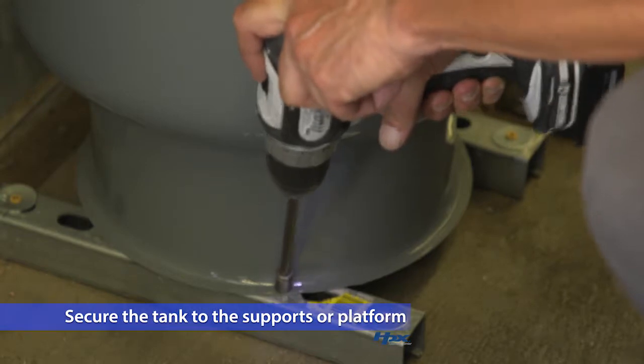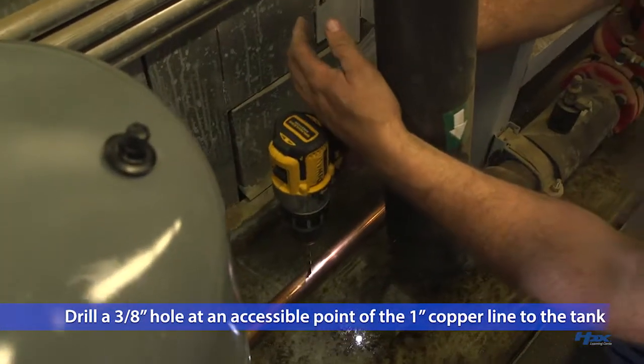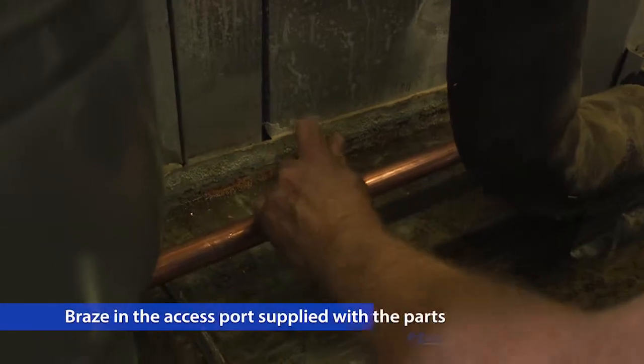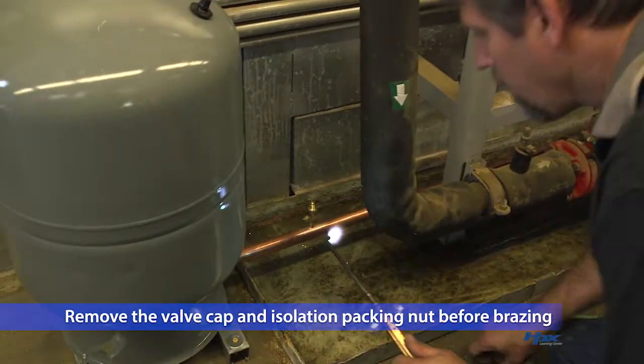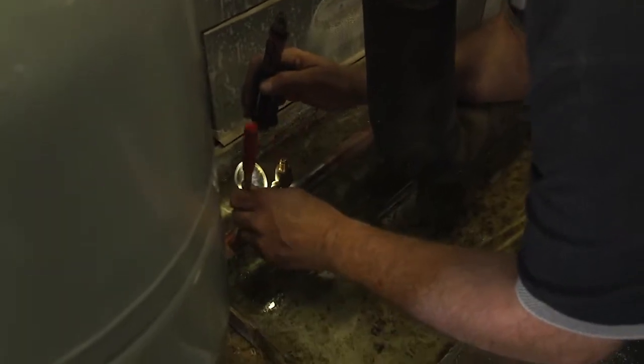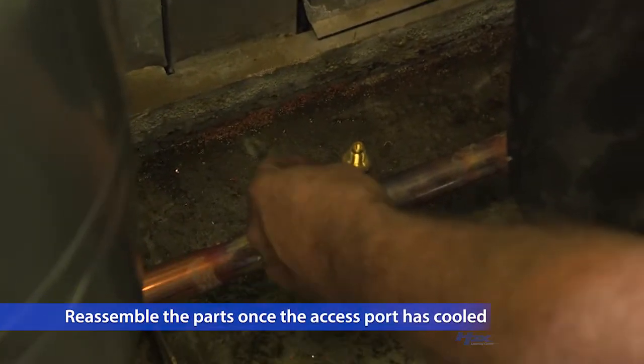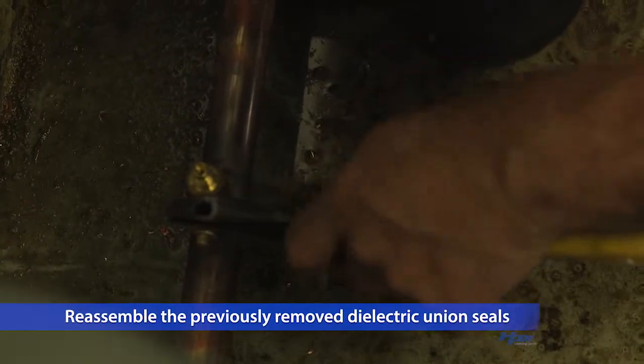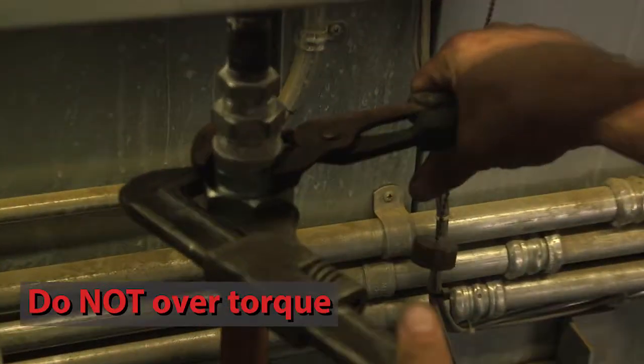You can now secure the tank to each of the supports or platforms. Drill a three-eighths inch hole at an easily accessible point along the horizontal one inch copper line to the tank. Then, braze in the quarter inch flare access port that was one of the parts supplied by Hill Phoenix. Be sure to remove the valve cap and isolation packing nut before brazing to prevent damaging them. Reassemble those parts when the brazed access port has sufficiently cooled.